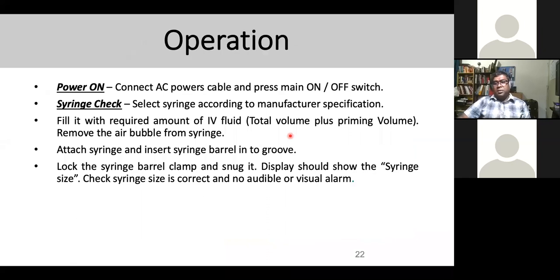Operation, normally you're going to connect the infusion device or syringe pump to the power line, and you're going to turn it on and check. If you're using a syringe pump device, you need to choose the syringe according to manufacturer specification and fill with the required IV fluid, total volume plus the priming volume, and remove the air bubbles from the syringe, and attach the syringe into the barrel groove and lock the syringe barrel clamp and snap, and set the syringe size accordingly.